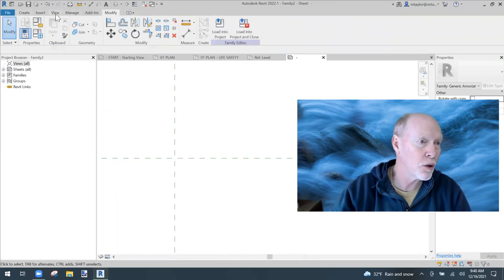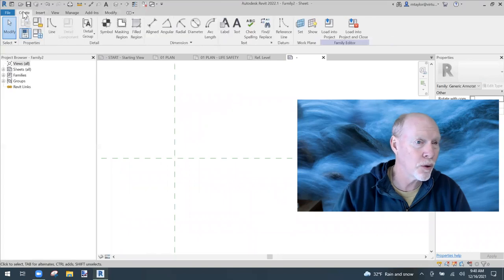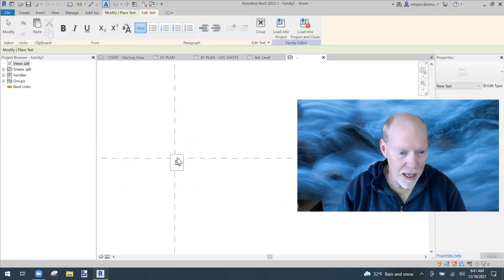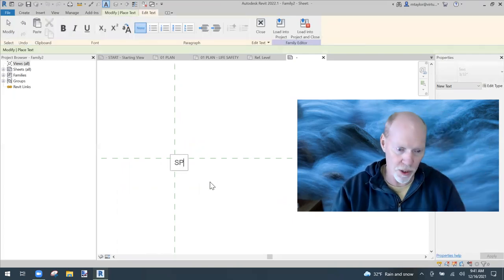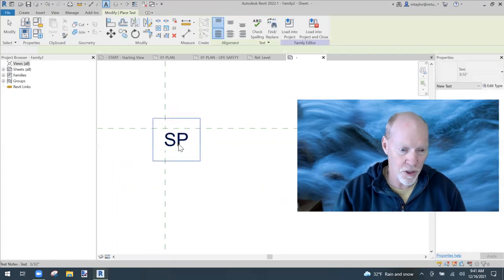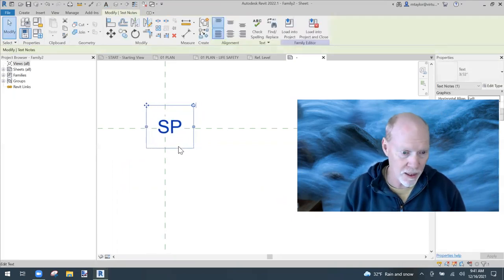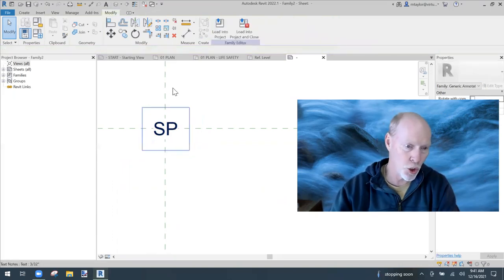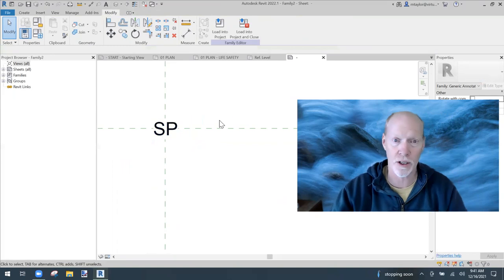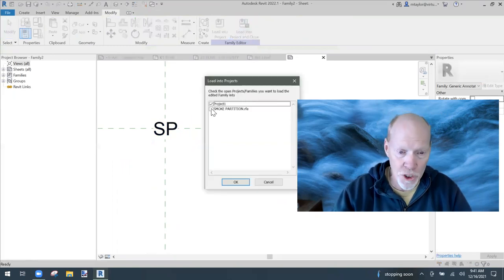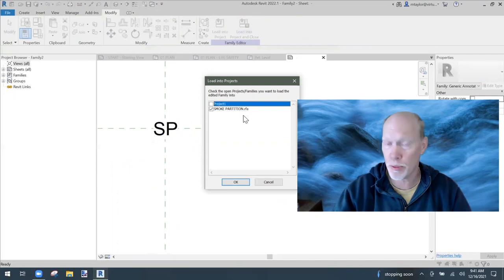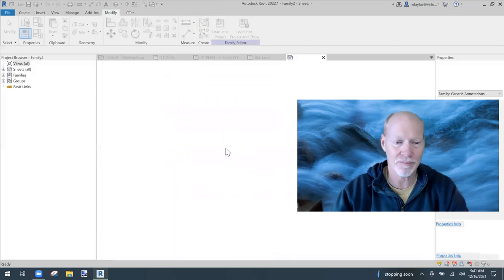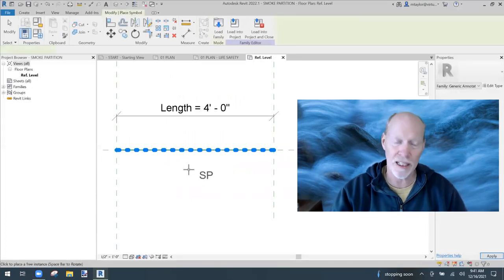In the generic annotation family, go to Create, Text, and type 'SP' for Smoke Partition right at the center of the crosshairs. Scootch it around so it sits at the center. Now load it into the Smoke Partition family — not into the project yet. When asked to save, don't worry about it. Now the SP label is sitting over the family.